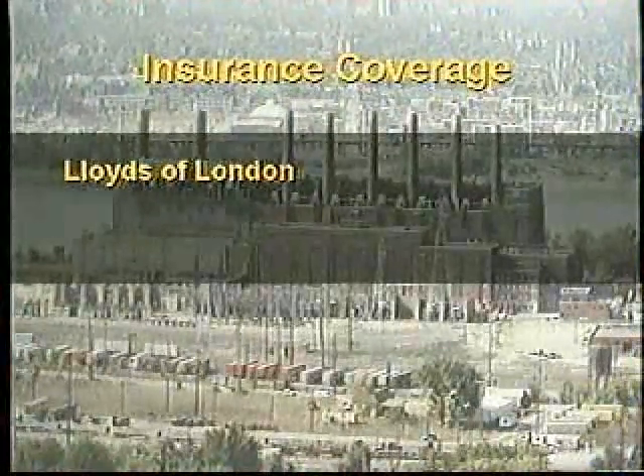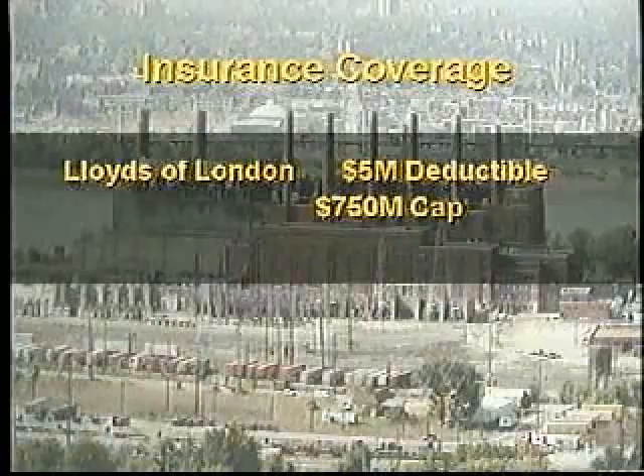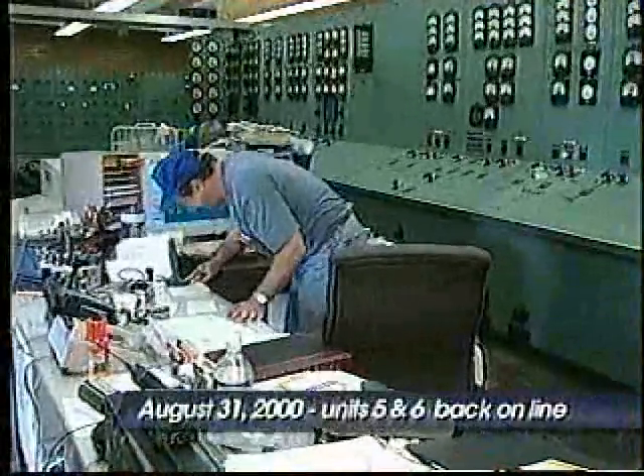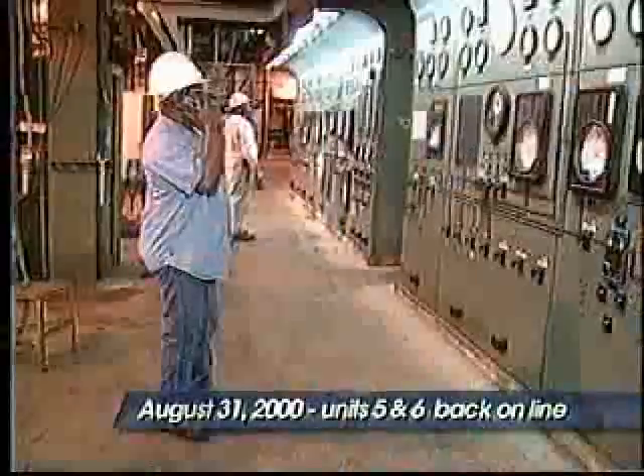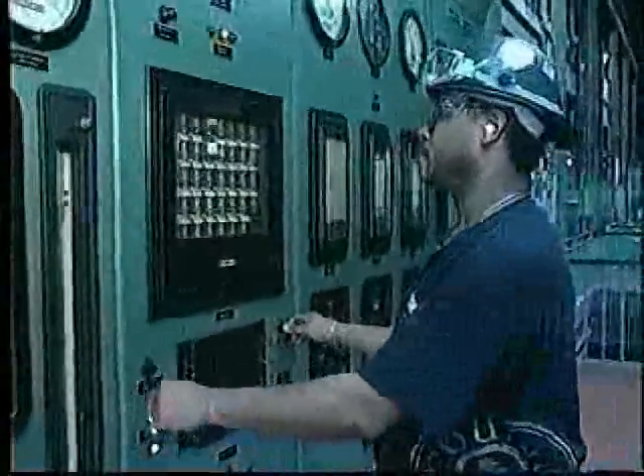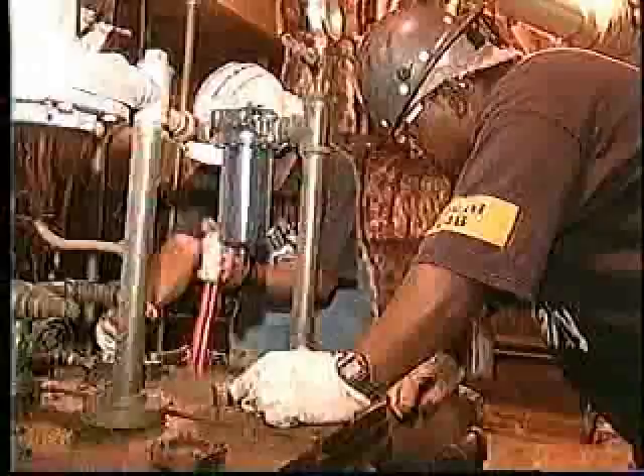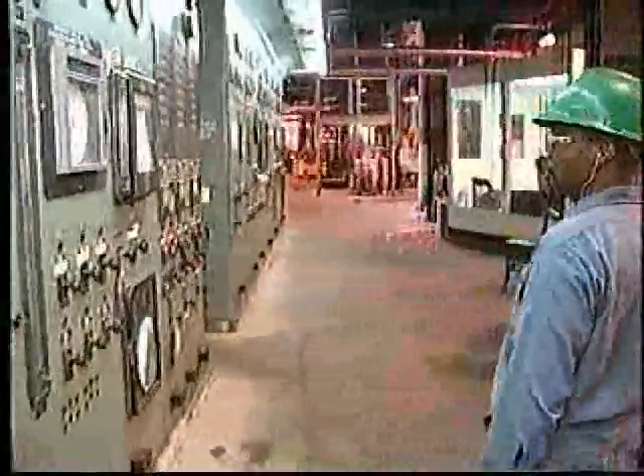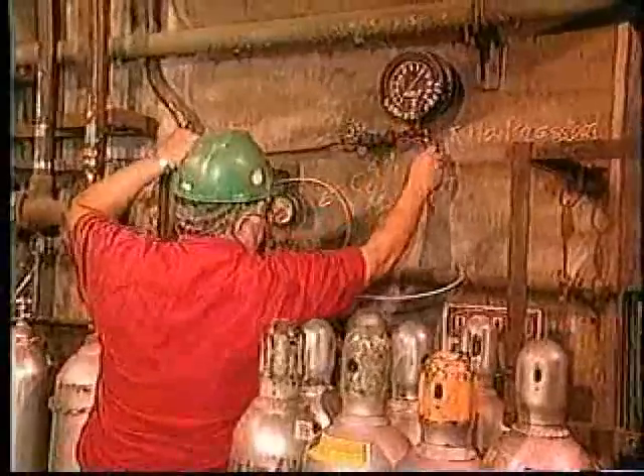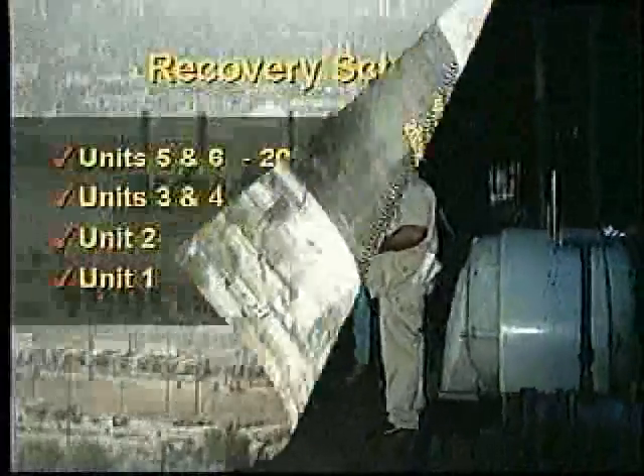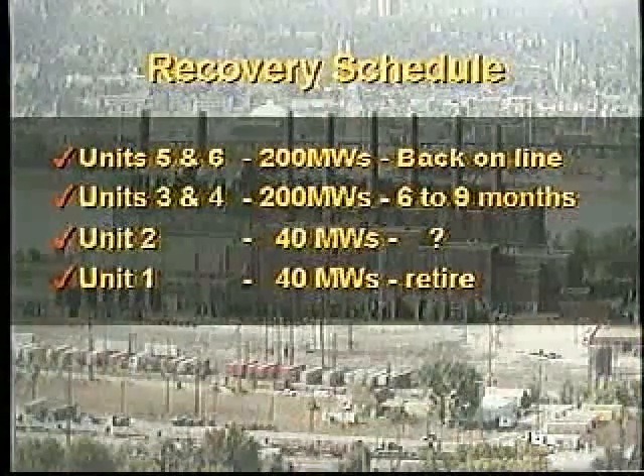We do fortunately have insurance coverage. This insurance coverage is provided by Lloyd's of London. This policy provides coverage of a $750 million cap with a $5 million deductible, and it also includes asset replacement. The recovery schedule for Venice plant is as follows. Units 5 and 6, which is 200 megawatts, or half of the plant output, we have back online. Units 3 and 4, which is worth 200 megawatts, will take about 6 to 9 months, primarily to get replacement transformers. Unit 2, which is 40 megawatts, is still under review to determine the complete damage and whether Unit 2 should be retired or restored back to its full output. Unit 1, which is 40 megawatts, will be retired.